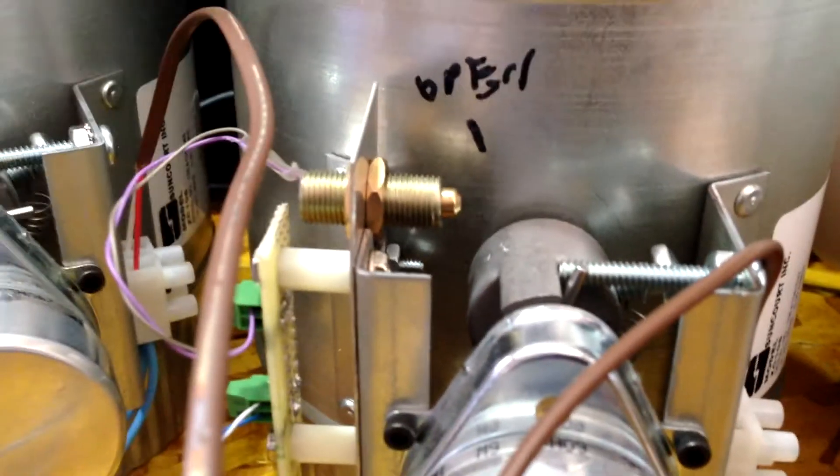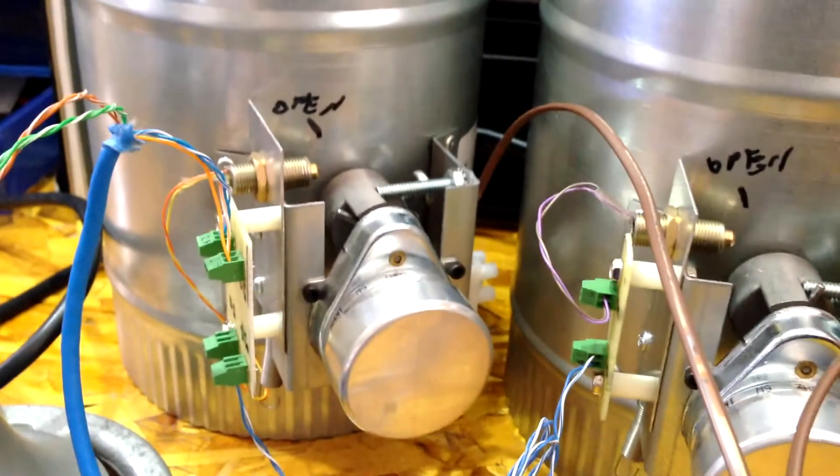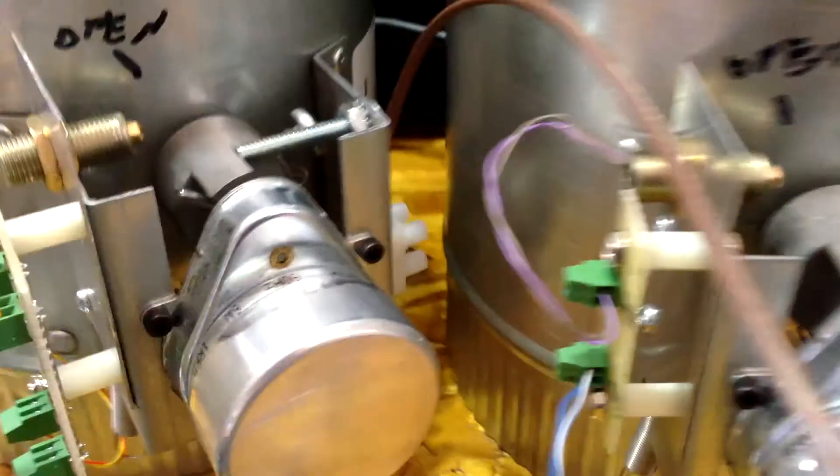So, let's shut that off, put it back in automatic. So yeah, so that way I get an actual status of the reed switches, and instead of delaying it for everything else, once it detects that the thing is open, that one of the dampers is open, then it'll turn the fan on, or close the other one, etc.